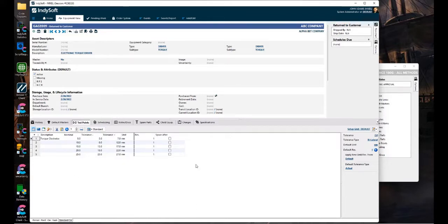So based on customer needs, you can set up these test points as tabs, and then when you go to calibrate, particularly using the scripting capabilities, you can limit that. Okay, if my customer equals Ferrari, for instance, then it would only allow me to use this tab. Typically, that would be an advanced situation, but it is possible.